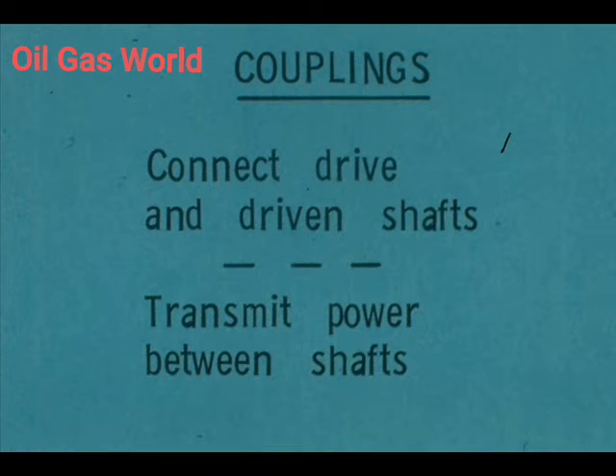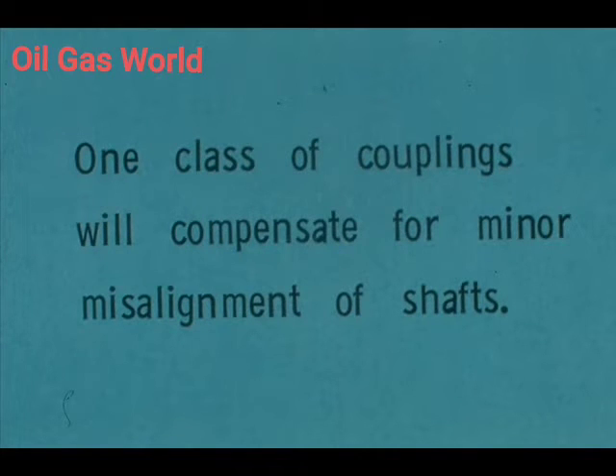As we mentioned earlier, couplings are used to accomplish two basic objectives: to connect a drive and driven shaft, and to transmit power between the shafts. However, couplings are also used for other purposes. One class of couplings is designed to compensate for minor misalignment between the rotating coupled shafts — referring only to minor misalignment, not major problems.